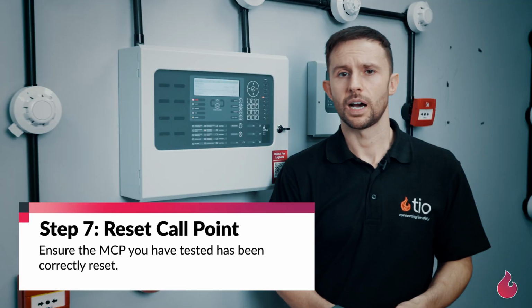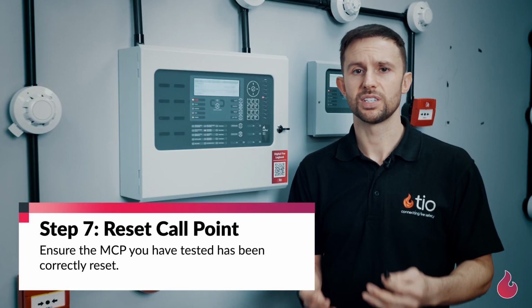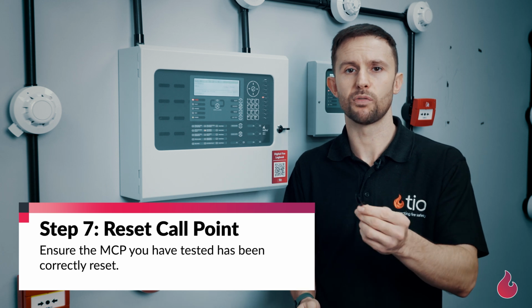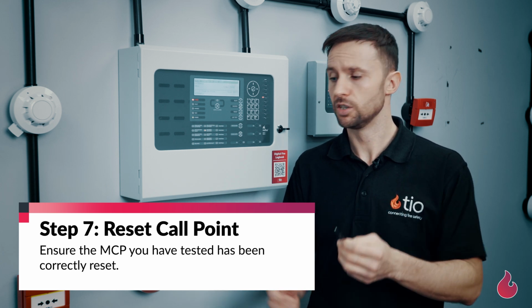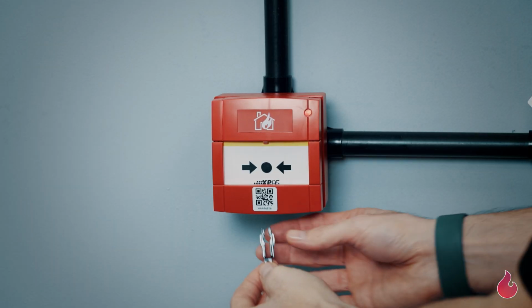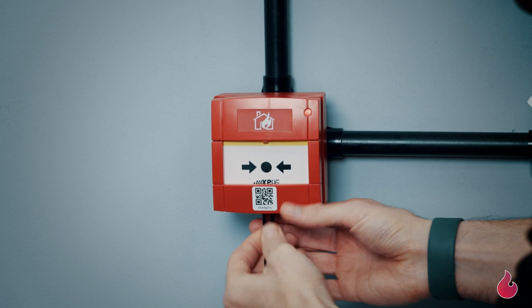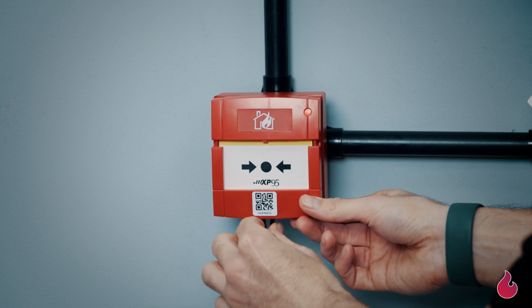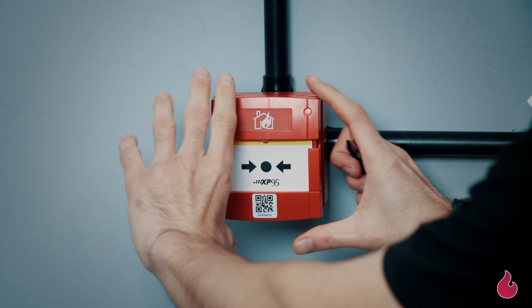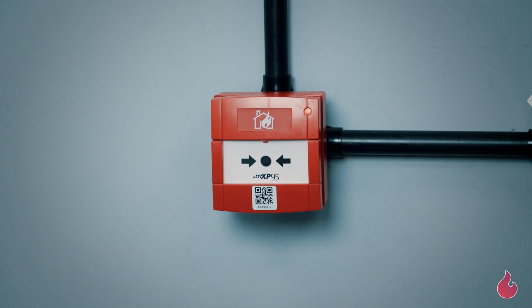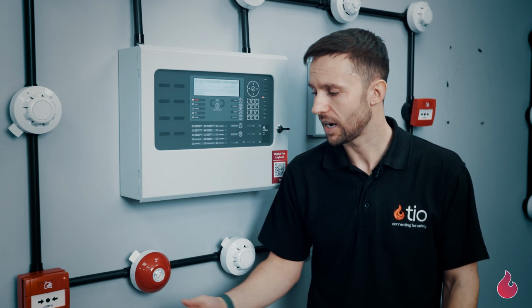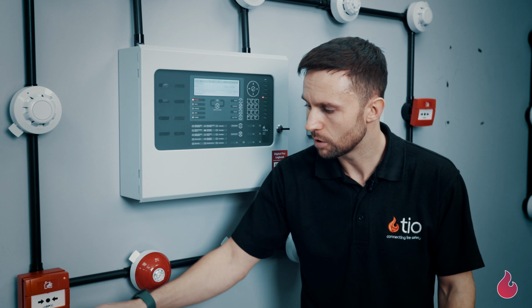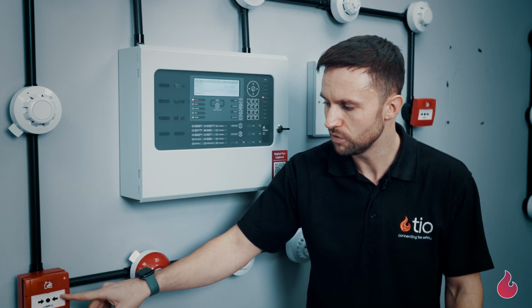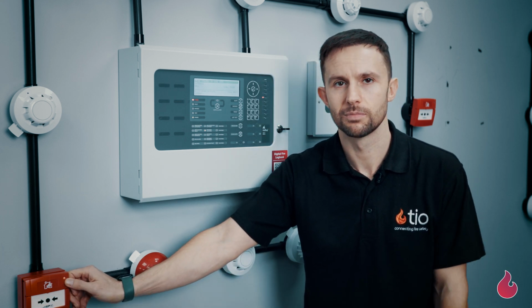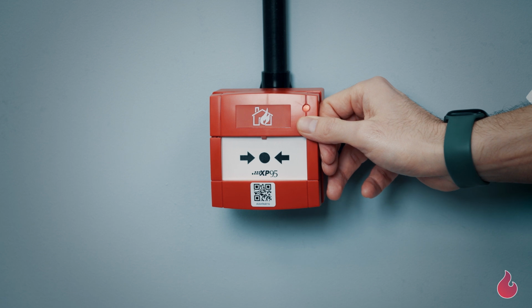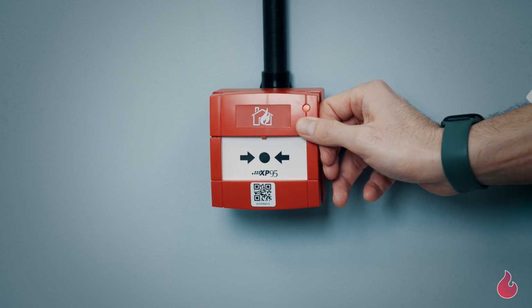Once you've successfully checked that your connected systems have activated, we now need to reset the call point that we activated earlier. As this particular call point has a resettable element, I'm going to use the key that was provided by my fire alarm maintenance company to reset the call point. First, I'm going to put the key in the bottom of the call point, pull the drawer down, wiggle the key out, and then hold the four corners to squeeze together. Now that the call point has been successfully reset, you'll notice that the yellow bar along the top has been removed, but the red LED still remains. The red LED on the call point will remain lit until you reset the fire alarm panel.